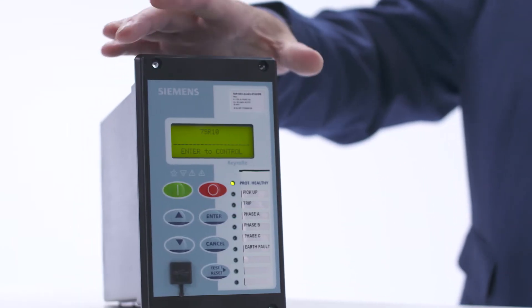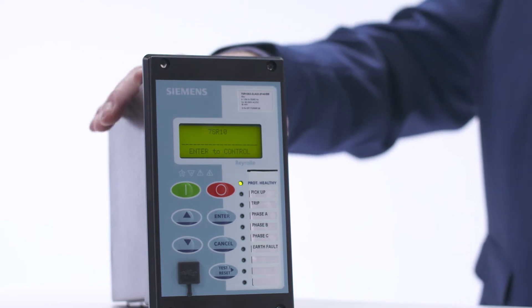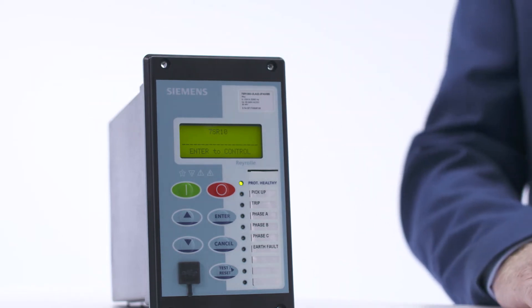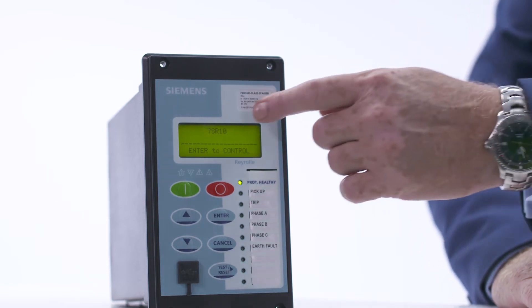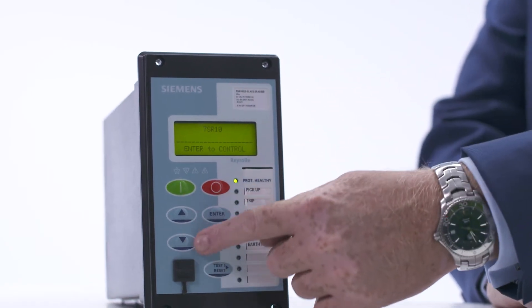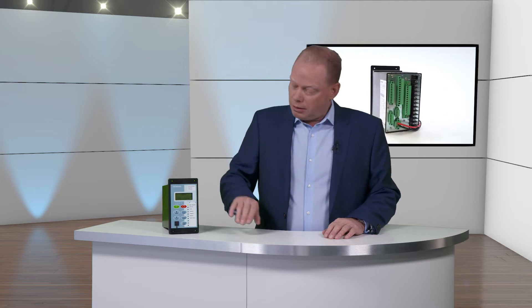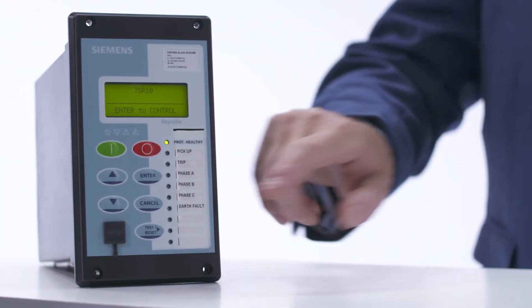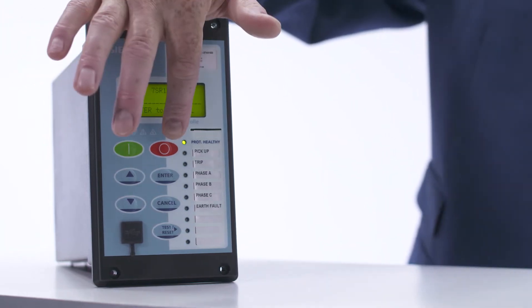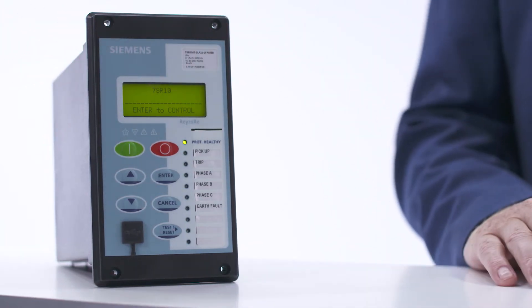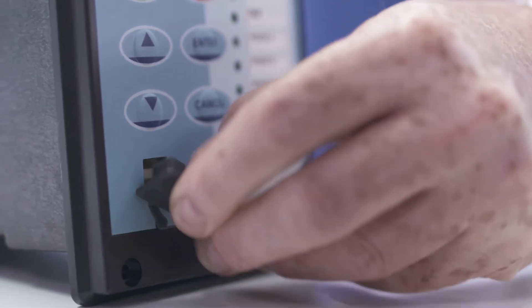Let's take a closer look at the 7SR10 hardware. The 7SR device is a 4U high, size 4 width with a moulded enclosure. The front of the device includes a display and push buttons that can be used to program the relay and view fault records and instrumentation. Nine LEDs provide the relay status information and there are open and closed push buttons for circuit breaker control. Also on the front of the device is a USB port, which can be used for connecting to a PC.